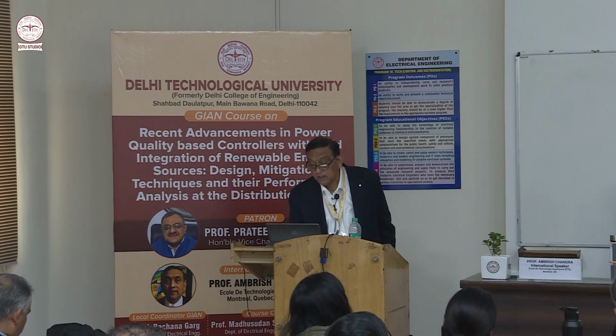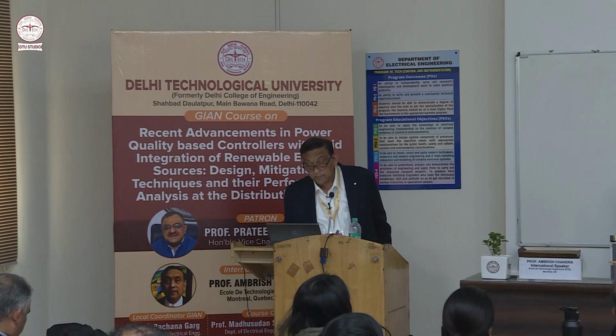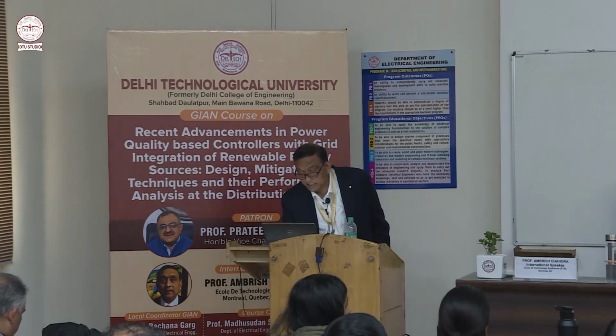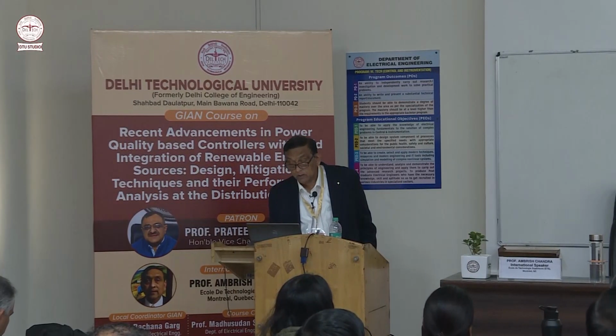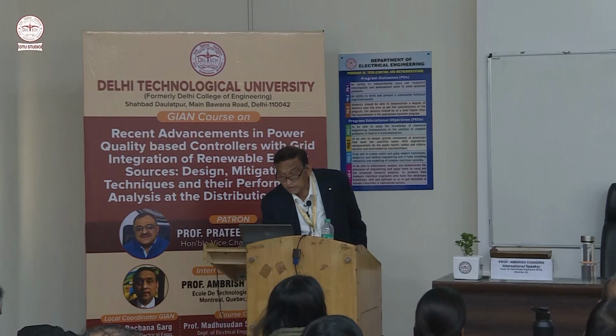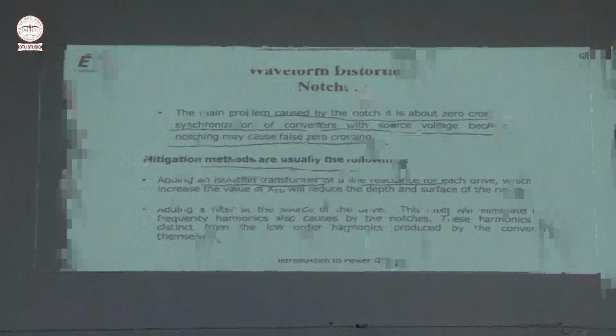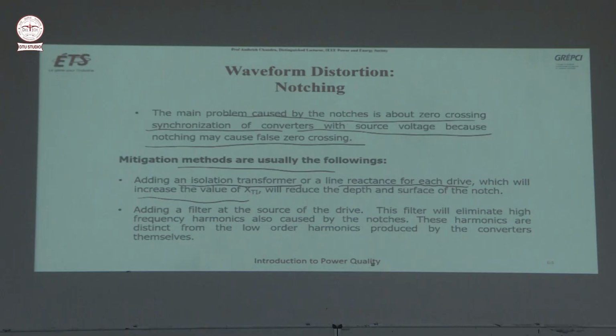Notches are about zero crossing synchronization with source voltage, because notching may cause false zero crossing. For example, here this depth, suppose it goes like this, then it may be seen as a zero crossing, and your converter may trip. Mitigation methods: an isolation transformer or a line reactor for each drive, which will increase the value of XTI and reduce the surface of the notch. Adding a filter may solve the problem.